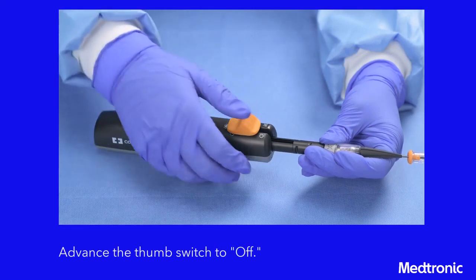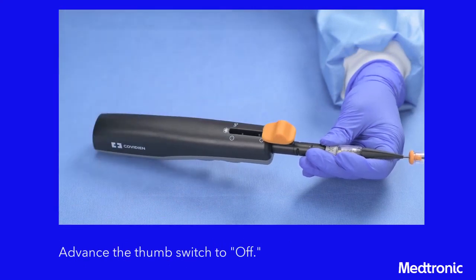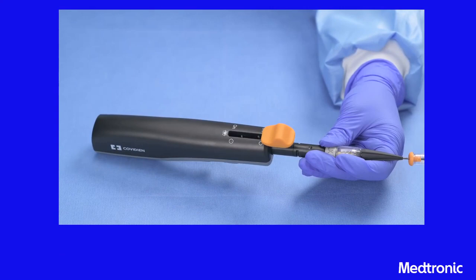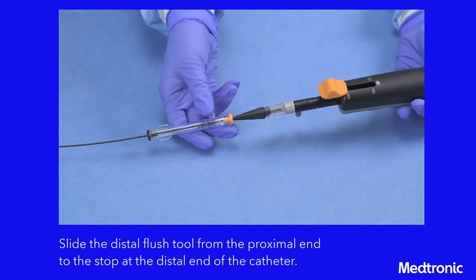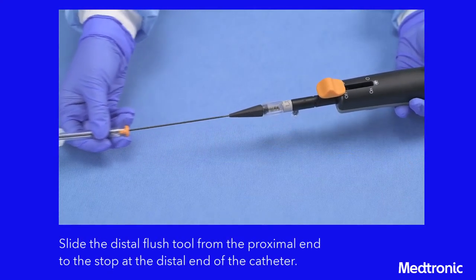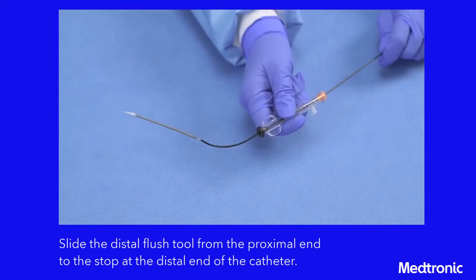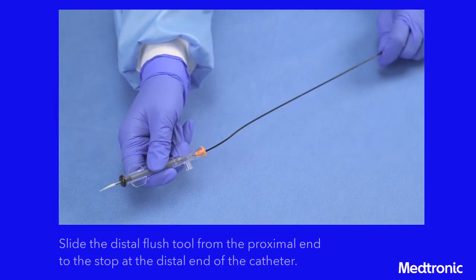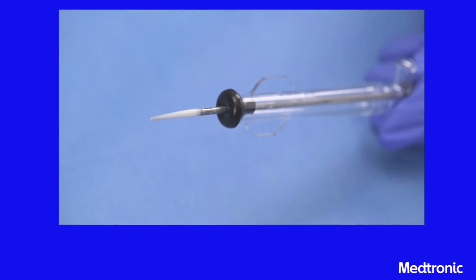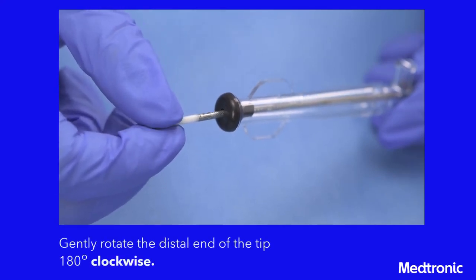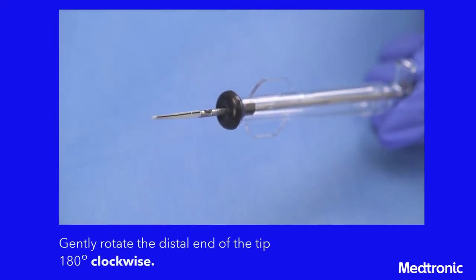Next, advance the thumb switch to the off position to close the cutter window, and slide the distal flush tool from the proximal end to the stop at the distal end of the catheter. The flush window in the catheter tip will be visible outside the distal flush tool seal. Gently rotate the end tip 180 degrees clockwise to open the flush window.